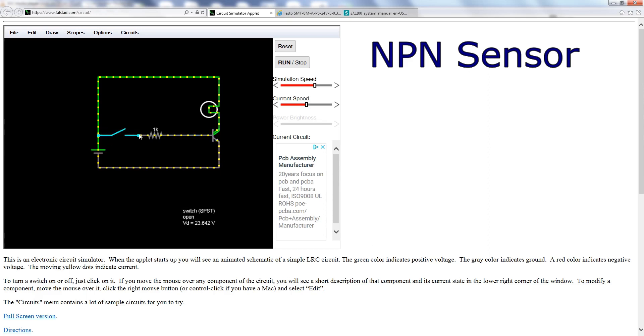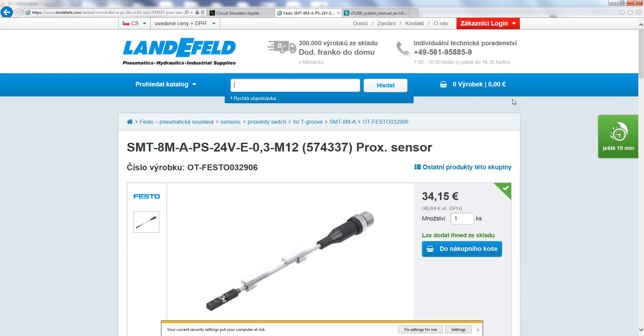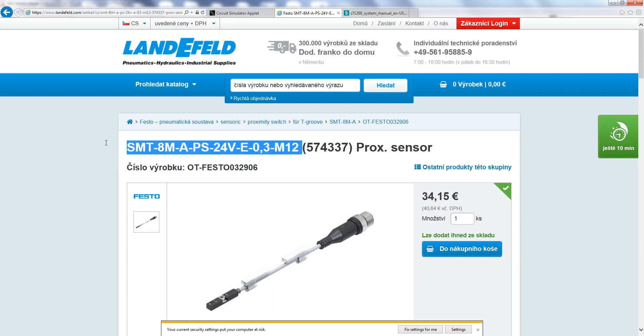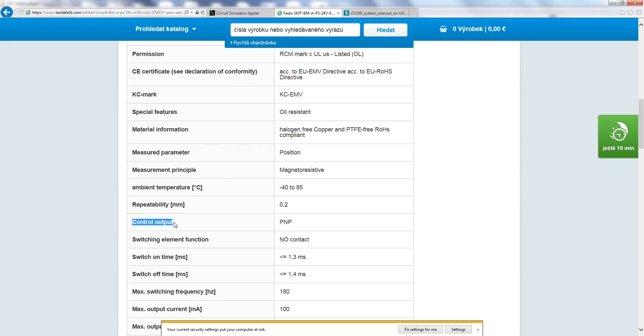If the sensor — which may be an inductive or proximity sensor — is switched on, it's switching the negative. Now a real-world example: let's say you have an air cylinder and you need proximity sensors to know the position — whether it's extended or retracted. The manufacturer gives you a part number, you go online and check the datasheet. You can see the control output is PNP, which means the sensor is switching the positive — the first letter is P.